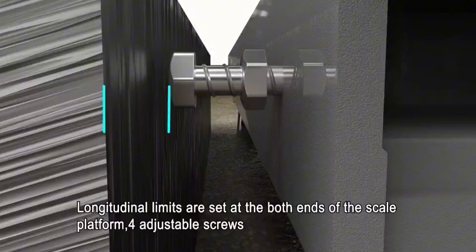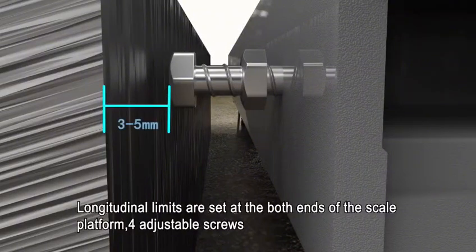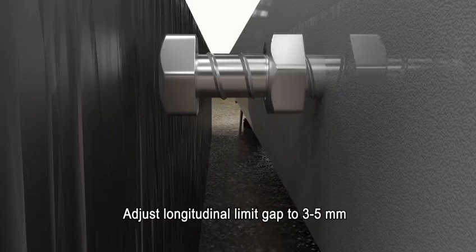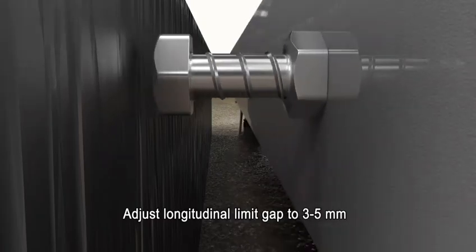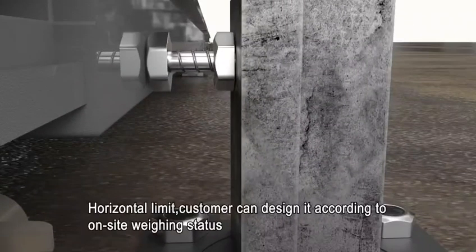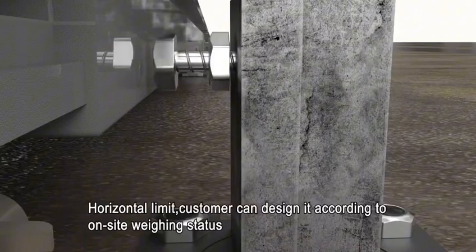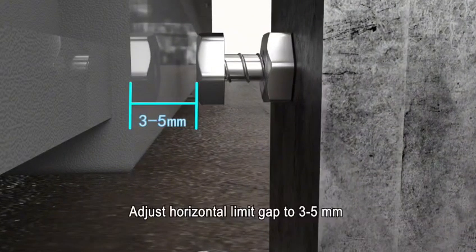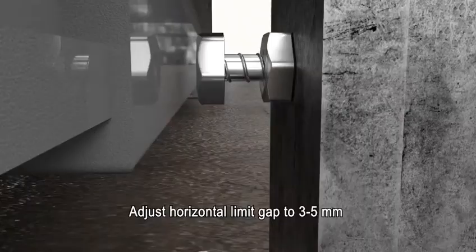Longitudinal limits are set at both ends of the scale platform with 4 adjustable screws. Adjust longitudinal limit gap to 3-5mm. Horizontal limit can be designed according to onsite weighing status. Adjust horizontal limit gap to 3-5mm.